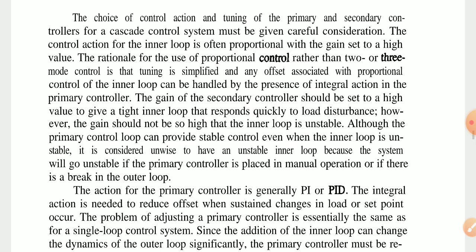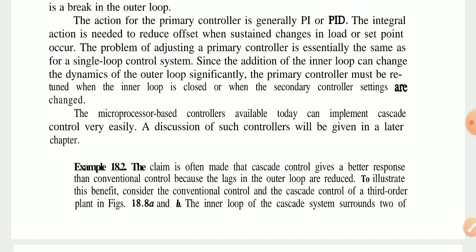The action for the primary controller is generally PI or PID control. The integral action is needed to reduce offset when a sustained change in a load or set point occurs. The problem of adjusting a primary controller is essentially the same as for a single loop control system, since the addition of the inner loop can change the dynamics of the outer loop significantly. The primary controller must be retuned when the inner loop is closed or when the secondary control system is added.